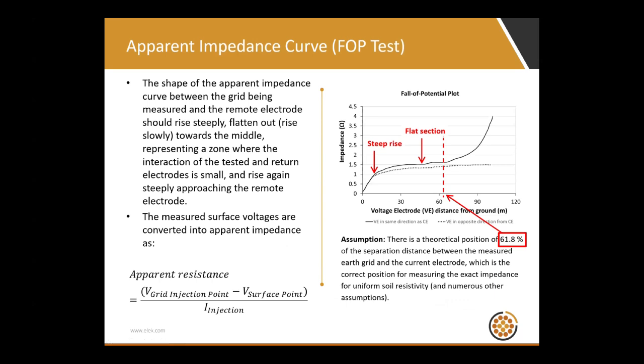So what's the output of a fall of potential test? Well, it's this apparent impedance curve. We inject current at a remote location, and we measure voltage on the surface of the ground, moving away from the grid towards the current injection point. In this typical fall of potential plot, we see that voltage rises, and so too does apparent impedance, as we move away from the grid. Towards the middle of the ideal plot, we will hopefully see a flat section. Then as we move closer to the injection point, we'll see a significant rise in apparent impedance and, of course, voltage.